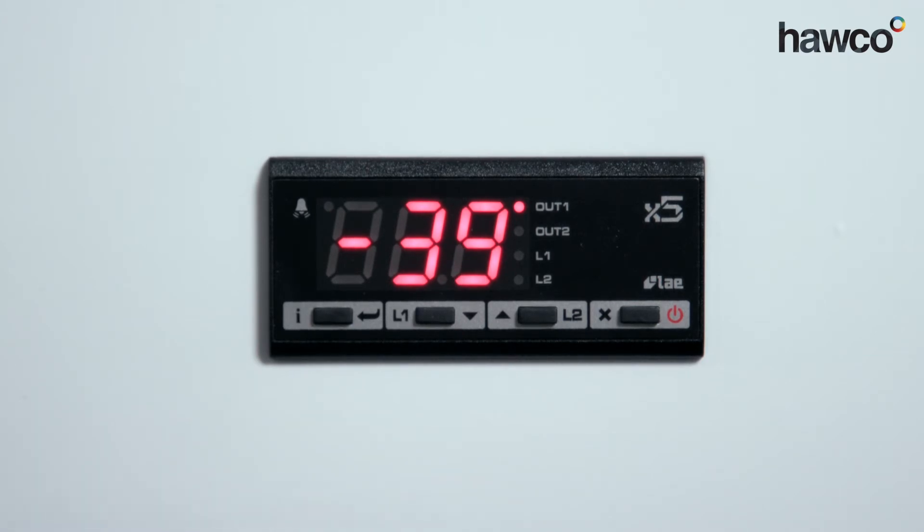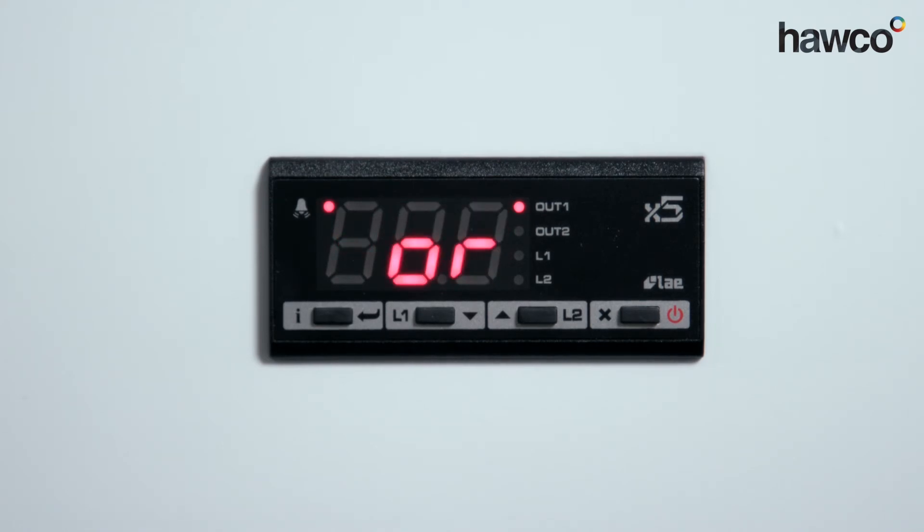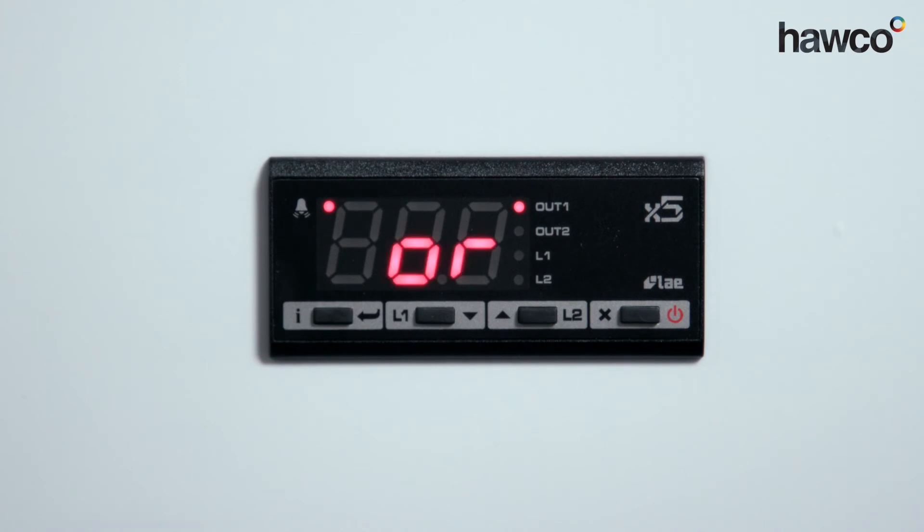This will do it regardless of demand, regardless of what temperature is in the room. It would only ever be on for three minutes, off for two minutes until we turn up on site, turn it off, replace the probe, and maybe reset the parameters.